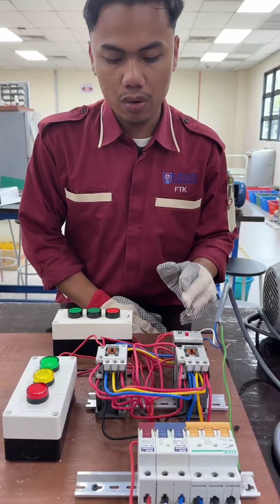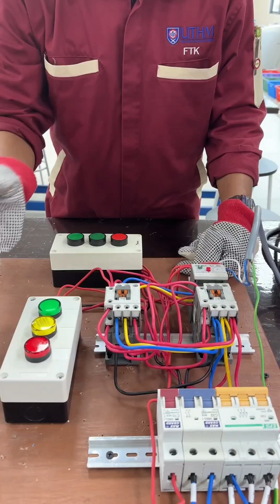First, we apply the connection. We take the single phase from the power supply and connect to the MCCB, 2 pole and single pole. First, we take one wire and connect it to the forward contactor. Then, as you can see, the connection is connected to the reverse, because we want to apply forward and reverse control to the motor.